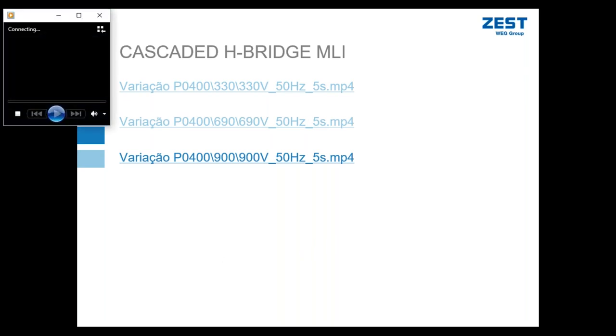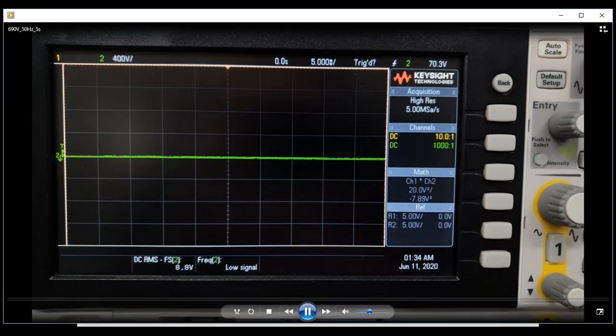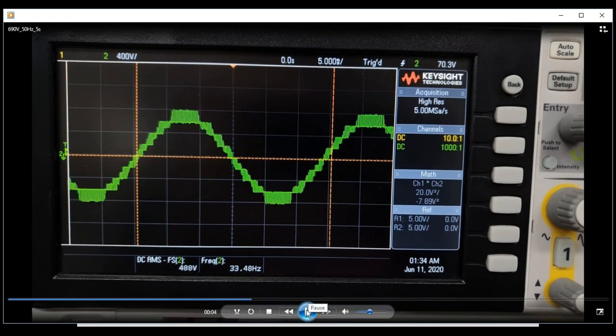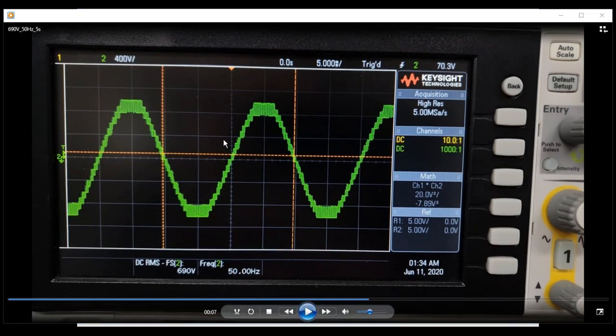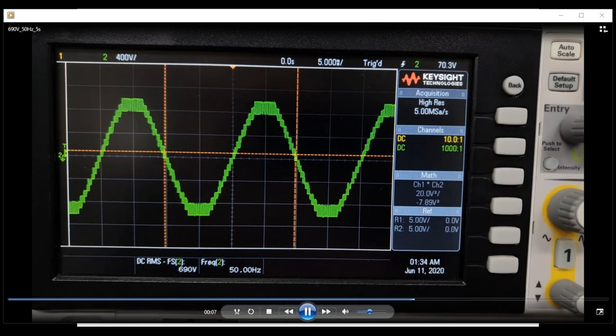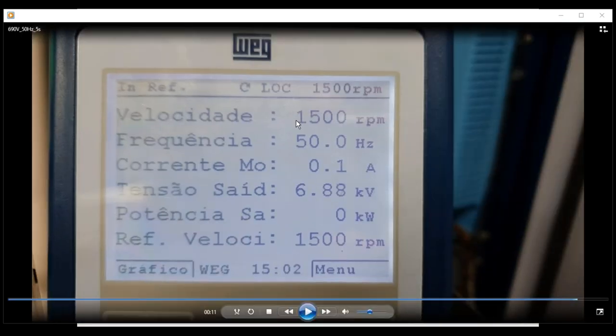Let me show you the same drive, but now supplying output power to a 6.6 kV motor, ramping up, getting to full frequency, full voltage. My scale is 1,000 times 400, so we have 4,000, 8,000. We're sitting at just below 10,000 volts peak, which is an RMS voltage of approximately 6.9 kV. So again we're running the motor at 1500 RPM. It's actually a 6.9 kV motor running at 50 Hertz. There's my output voltage just under 6.9 kV.